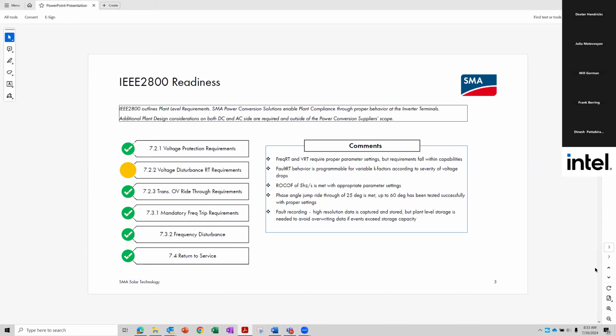And typically it is not the inverter that is the problem. It's typically the auxiliary equipment, the power supplies, the cooling fans, that really need to be protected from transient overvoltages. So at SMA, we have an option that adds a transient overvoltage suppression device to all of the auxiliaries. And with that option selected, we meet the transient overvoltage ride-through requirement.